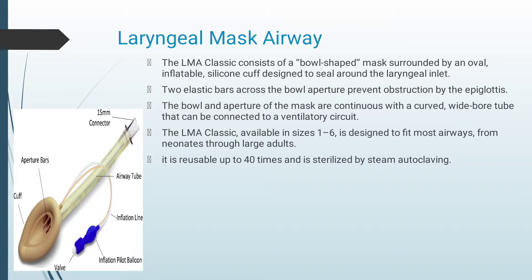To describe a common supraglottic airway device — the laryngeal mask airway. This is the LMA Classic. The LMA Classic consists of a bowl-shaped mask surrounded by an oval inflatable silicone cuff designed to seal around the laryngeal inlet. Two elastic bars across the bowl aperture prevent obstruction by the epiglottis. The bowl and aperture of the mask are continuous with a curved wide-bore tube that can be connected to a ventilatory circuit. The LMA Classic is available in sizes 1 through 6, is reusable up to 40 times, and is sterilized using steam autoclaving.